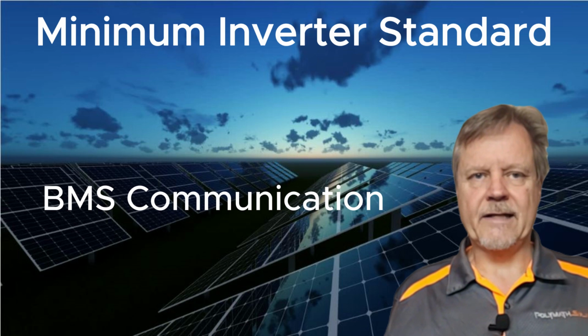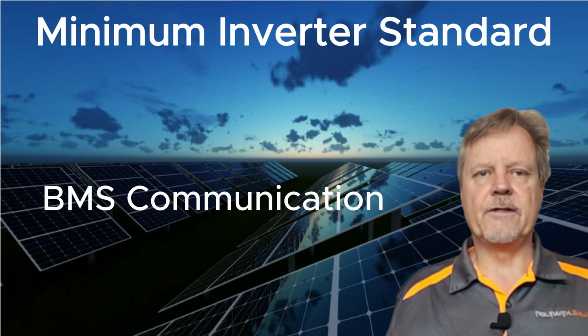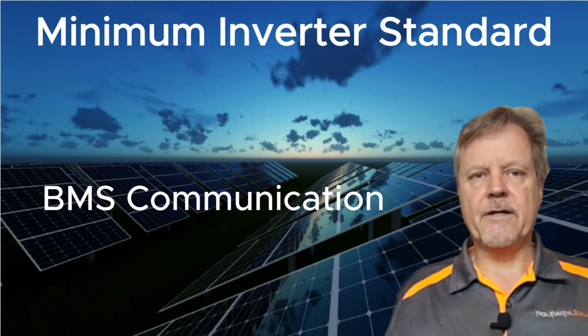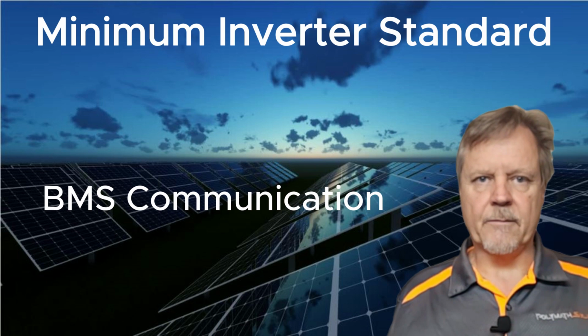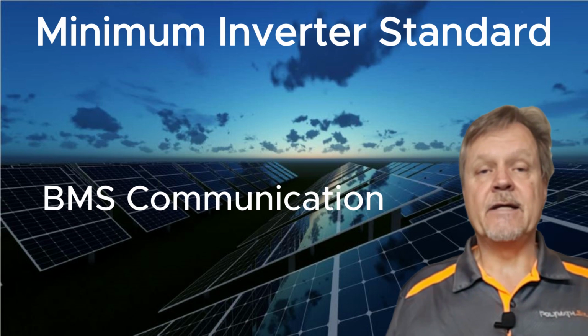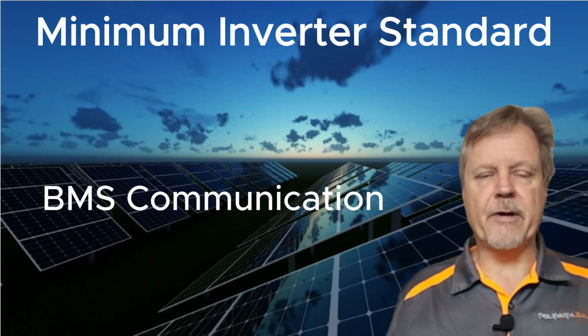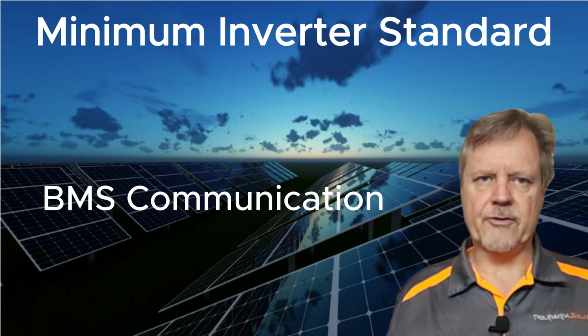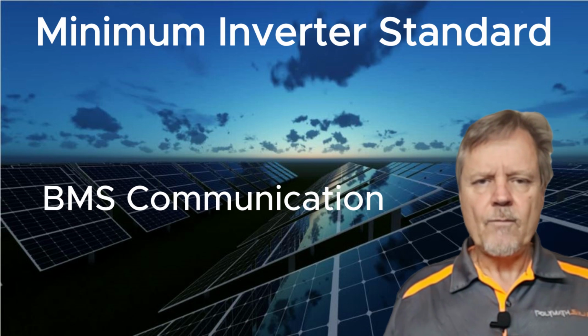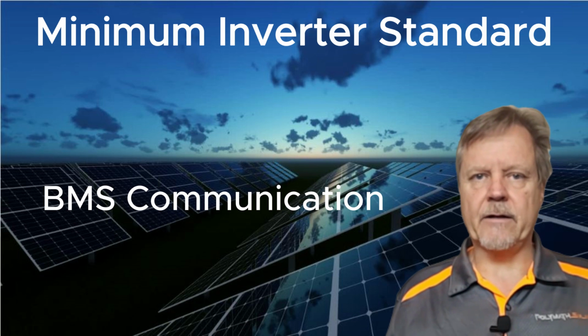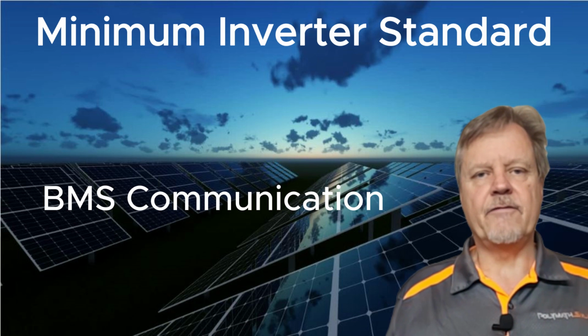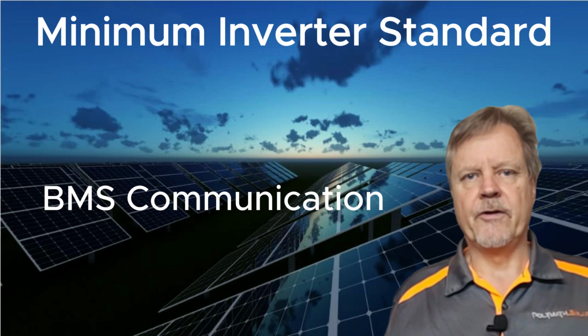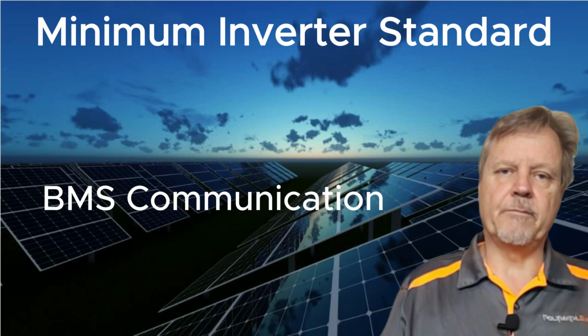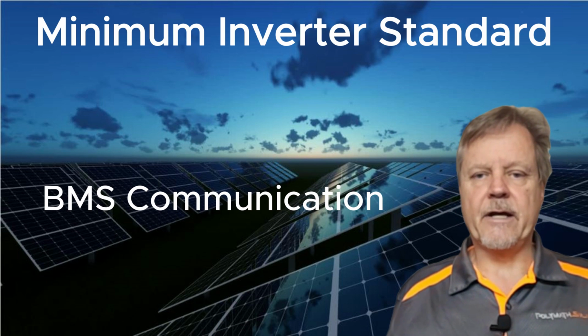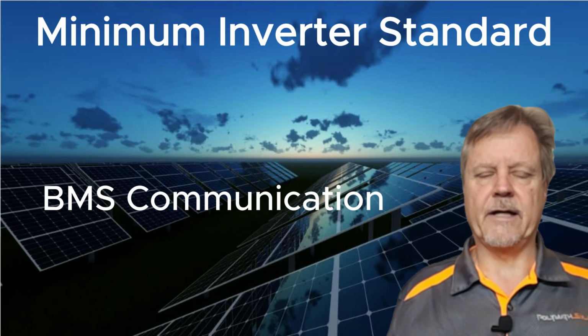So we also make it a minimum requirement that your inverter must communicate with the battery, with adaptive charging and adaptive management from the battery. The battery will specify what voltage it needs and how many amps it can handle charging or discharging, and that information must control the inverter. The inverter does not control the battery; the battery controls the inverter. That's the communication benefit of setting up your inverter and battery to communicate.